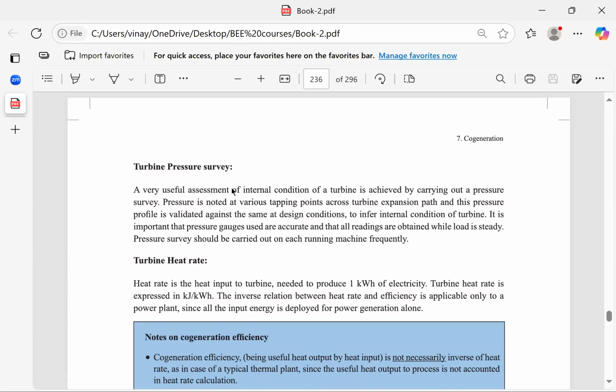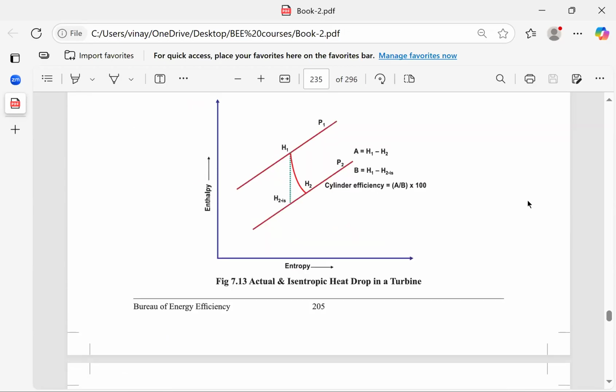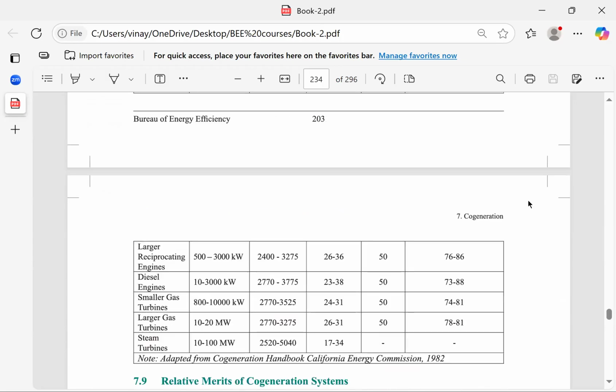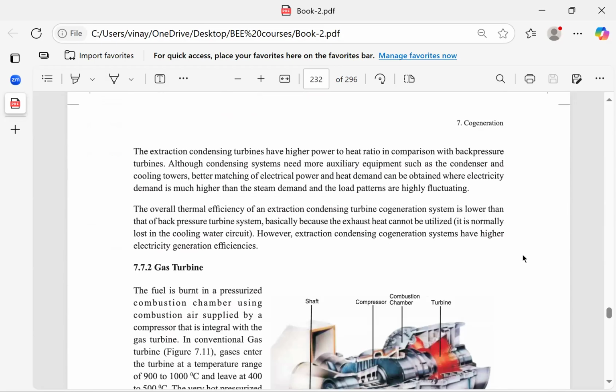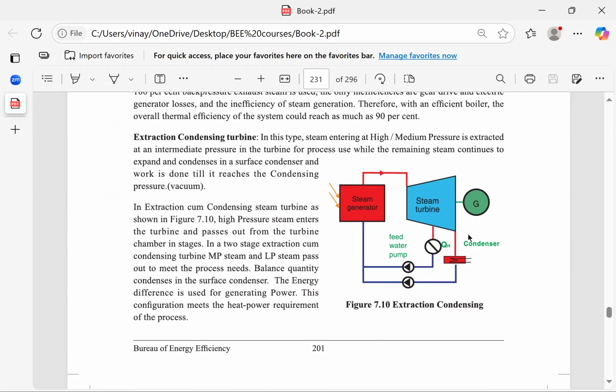Then turbine pressure survey - what is pressure survey? As I said, if this is the steam turbine we just saw, and this is a gas turbine, the pressure drops from the starting point, say 150 kg, to the end, say 5 kg, or even negative vacuum if it's a condenser. The pressure is gradually dropping from full pressure to negative pressure through the journey across the stages.